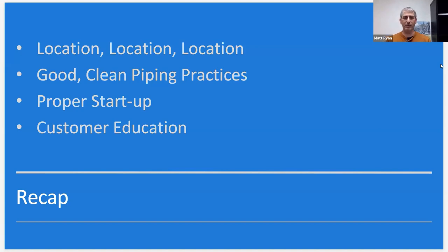And then clearances, making sure everything's clear, that the system can get good transfer of air. Good clean piping practices. Making sure it's dry, making sure it's clean. Don't drag it through the mud. Don't point it wide open up into the air and let it be a rain catcher. Using the right tools, going through the proper startup commissioning, which we'll dive a lot deeper into in the next one. And then customer education and making sure we're relaying the best way for the end user to use this new high-end system we put in.